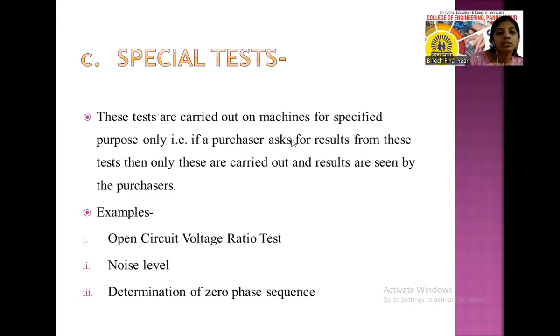So what is routine test? Routine test is carried out on each and every machine manufactured in an industry. Type test is carried out on a few machines - out of many machines, type test is carried out on only 2-3 or 4-5 machines. Special test is carried out as per the customer's requirement, and supplementary test is carried out to check the special performance of the machine.